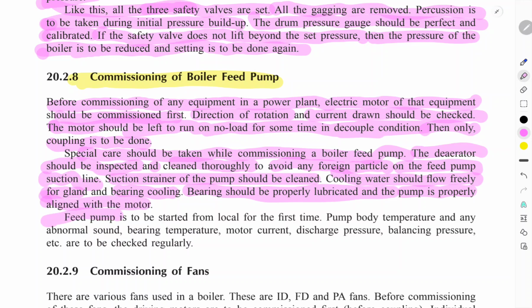The feed water pump is to be started locally the first time. Pump body temperature, any abnormal sound, bearing temperature, motor current, discharge pressure, balancing pressure, etc. are to be checked regularly.